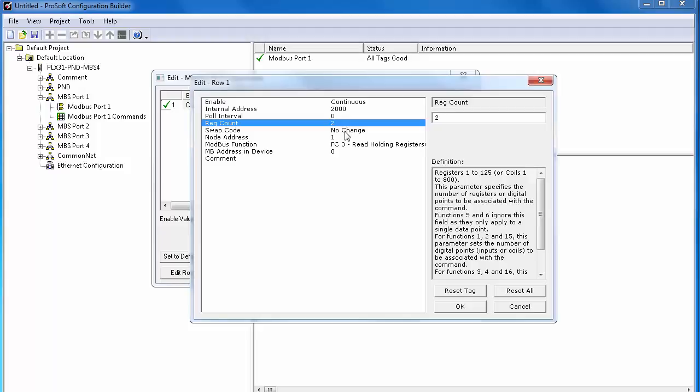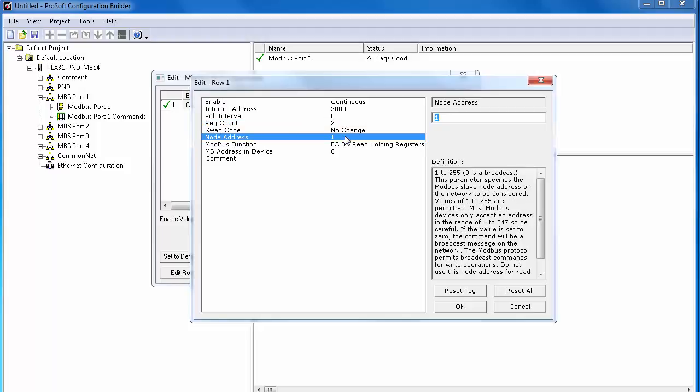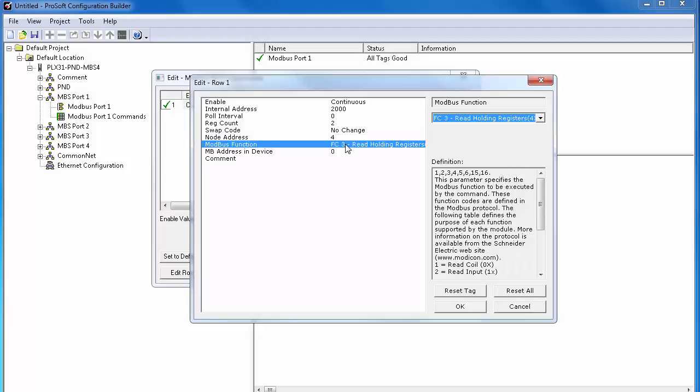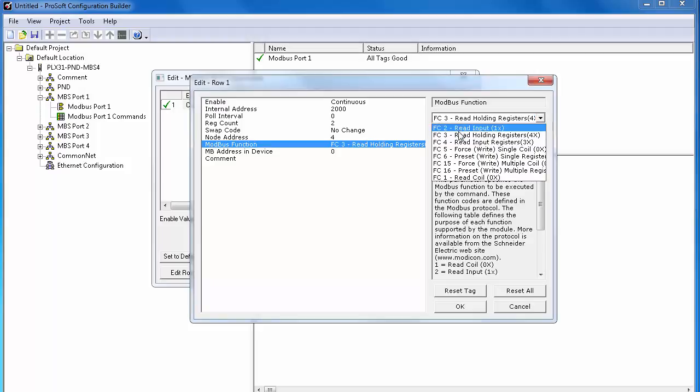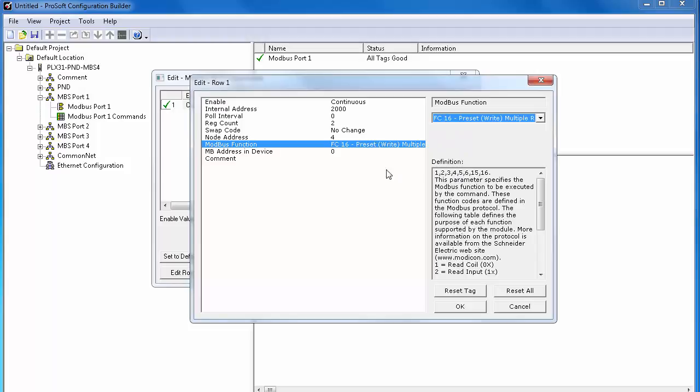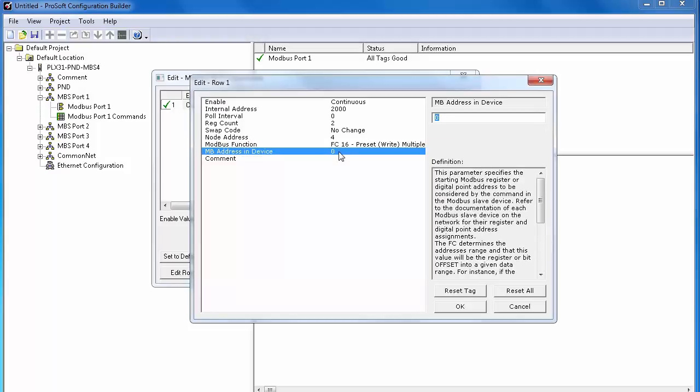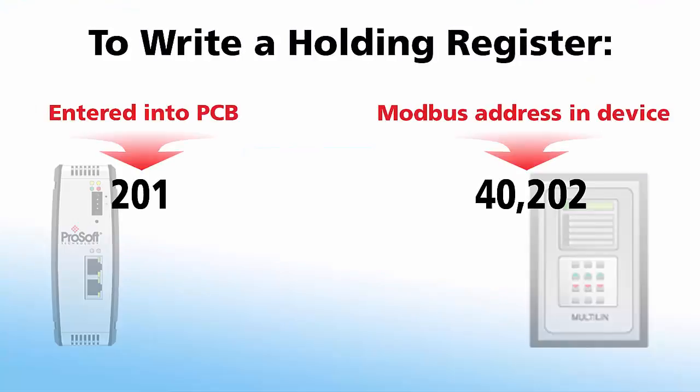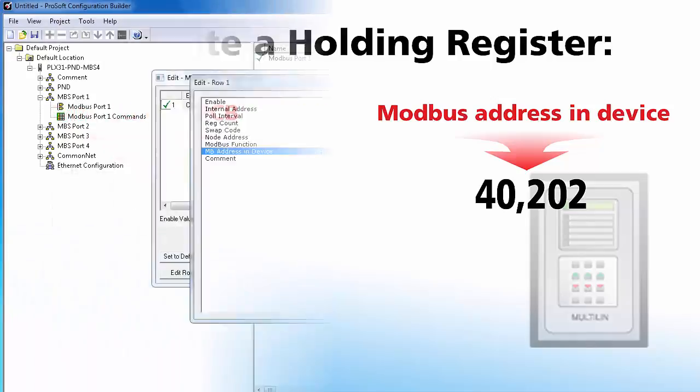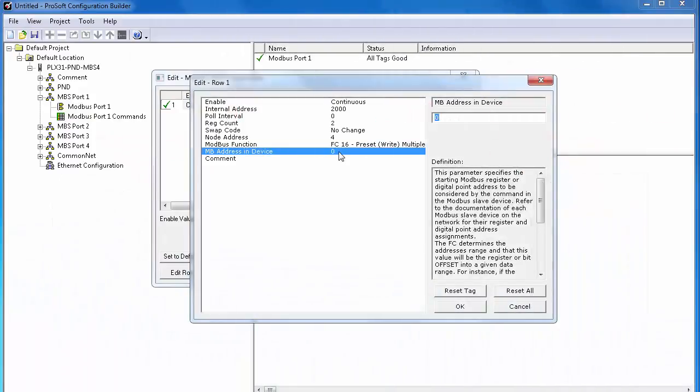For register count, we'll grab two words of data to accommodate a 32-bit floating point value. Node address will be 4. This is the slave address of the power monitor we're communicating with. Function code will be 16 to write multiple words. Modbus address in device will be the address in the power monitor that I want to write to, which is 40,202. The power monitor uses standard Modbus addressing. All holding registers will be located in the 400001 address range. Our gateway uses zero-based addressing. We'll just enter 201. And now we can click OK.